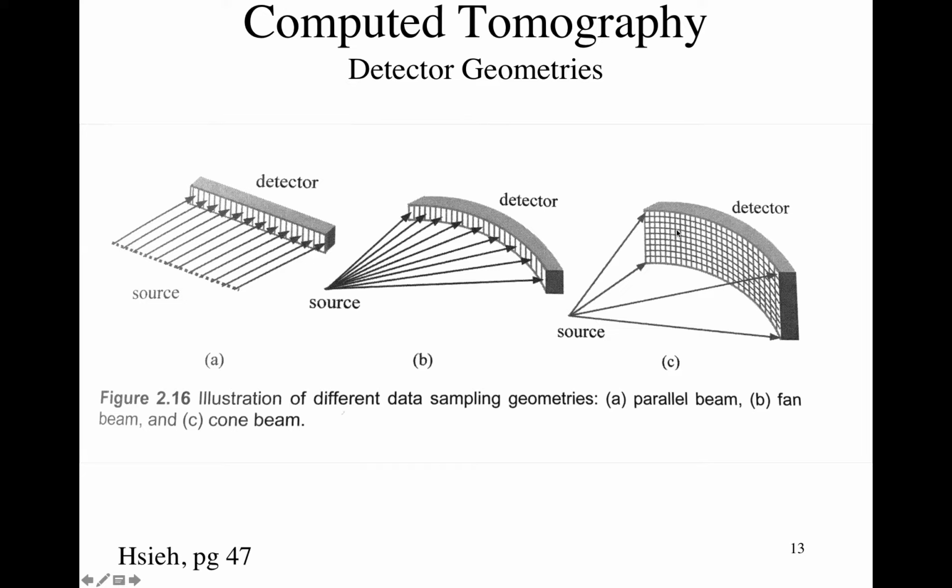And now the modern CT scanner actually has not only detectors in this direction, but it also has multiple slices being acquired simultaneously. A modern CT imaging system would have about 1,000 detectors in this direction and upwards of 256. The most common is 64 in this dimension, but now you can get 256, 320. So you're basically getting volume pictures, looking at different angles through the object.